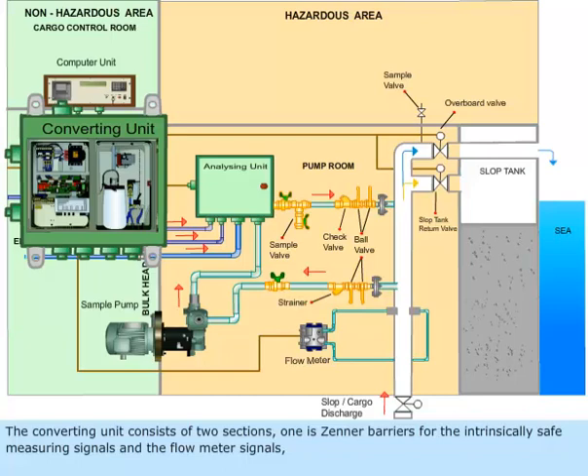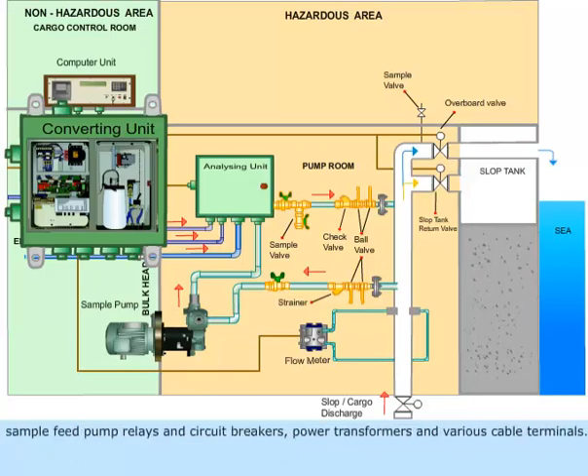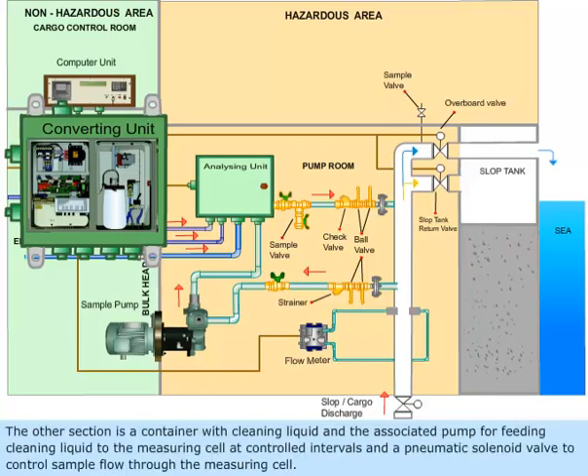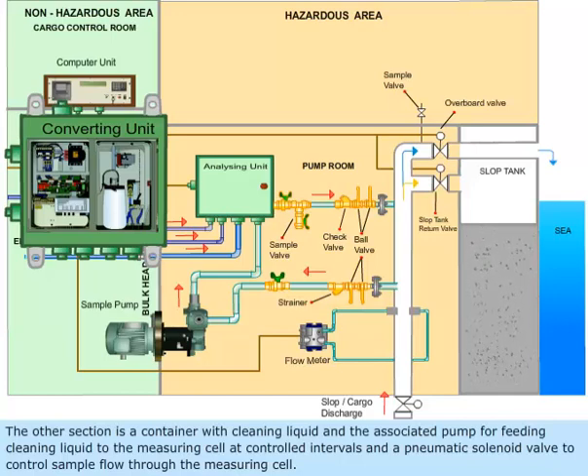The converting unit consists of two sections. One section contains Zener barriers for the intrinsically safe measuring signals and the flow meter signals, sample feed pump relays and circuit breakers, power transformers, and various cable terminals. The other section contains a container with cleaning liquid and the associated pump for feeding cleaning liquid to the measuring cell at controlled intervals, and a pneumatic solenoid valve to control sample flow through the measuring cell.